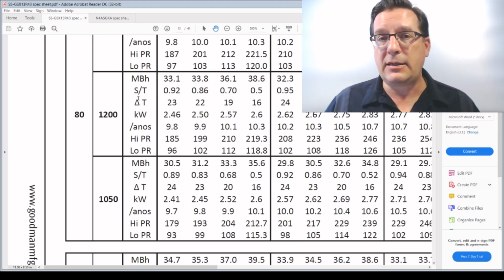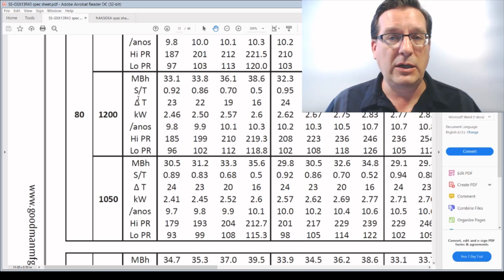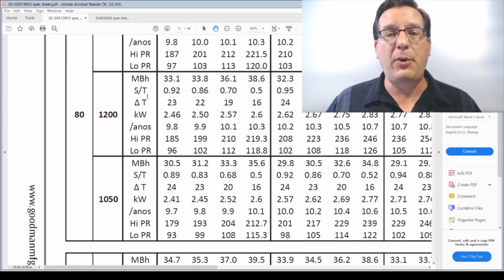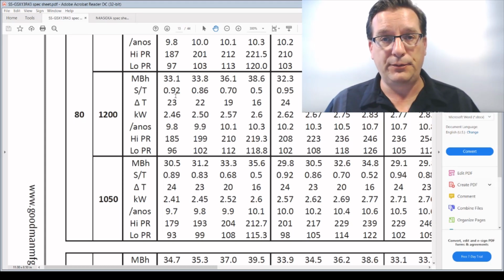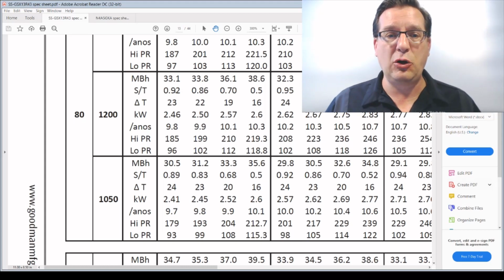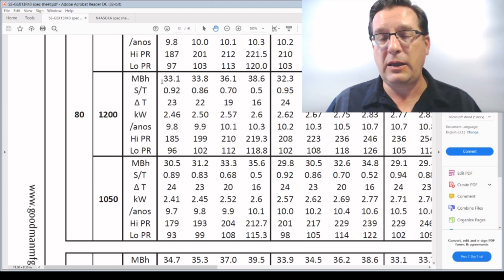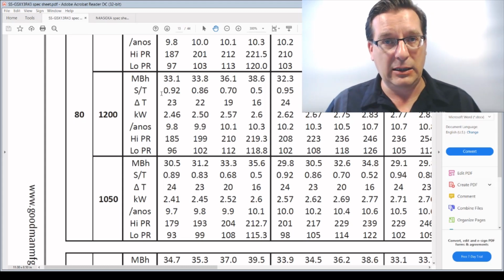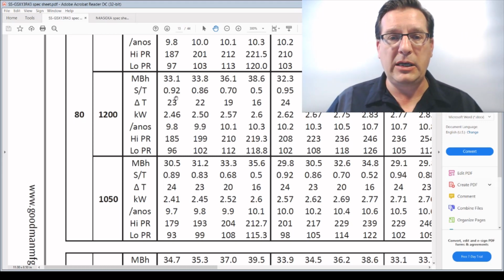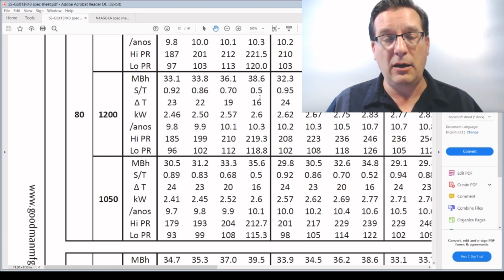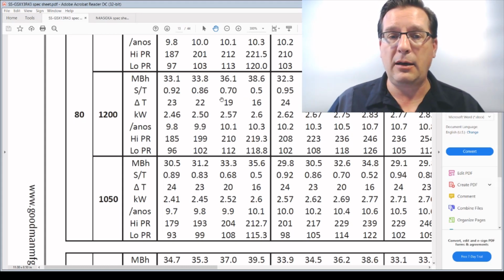S/T. This is the sensible heat ratio. What this means is a percentage or a ratio of the total. So this one is listed at 0.92. That means 92% of these 33,100 BTUs are going to be sensible heat absorption. Whatever is left over is latent heat absorption. And the sensible heat ratio will change depending on what the conditions are, and we'll look at that.